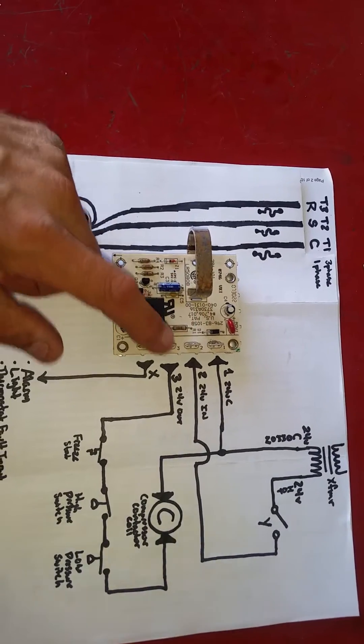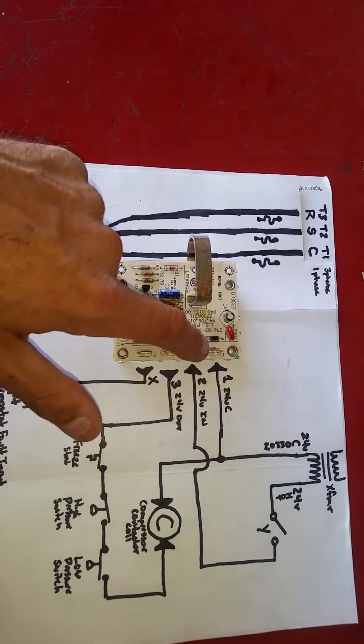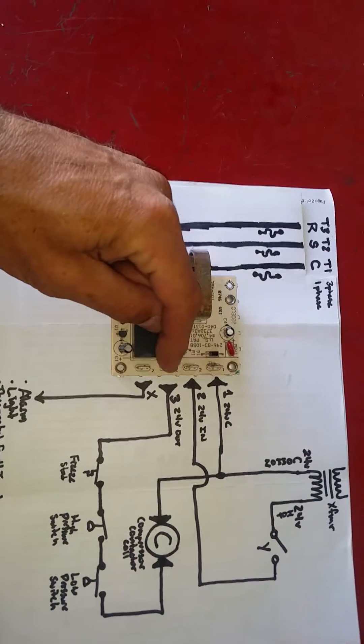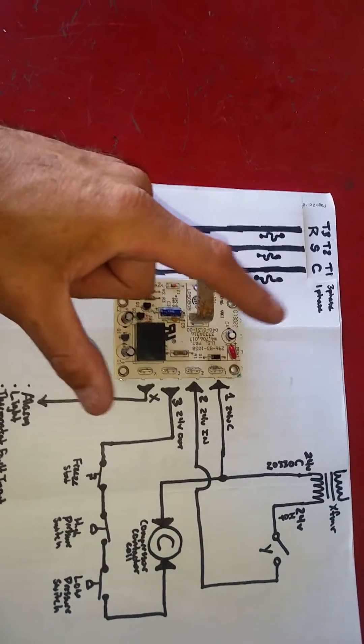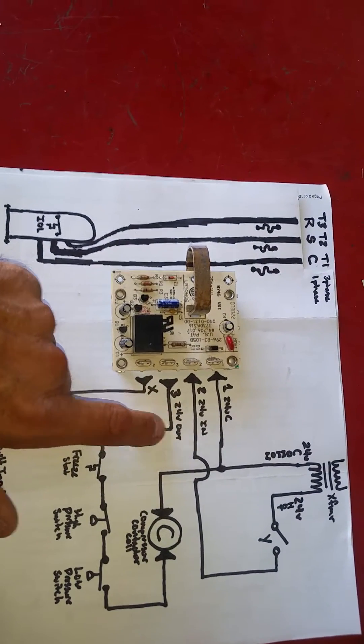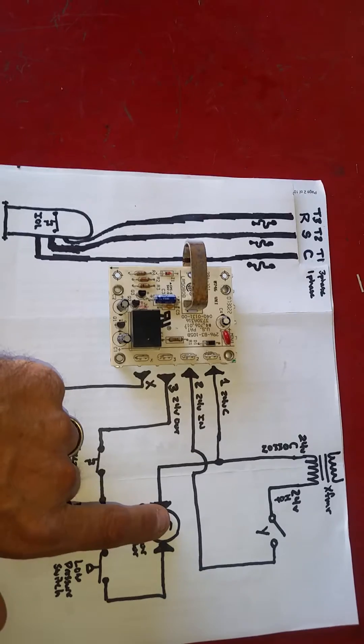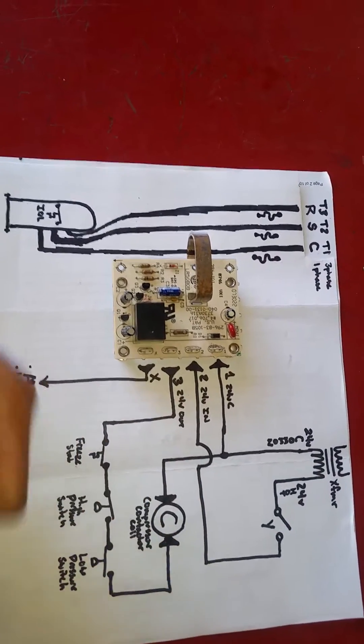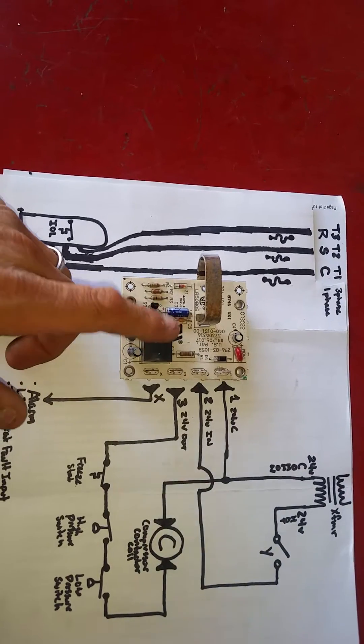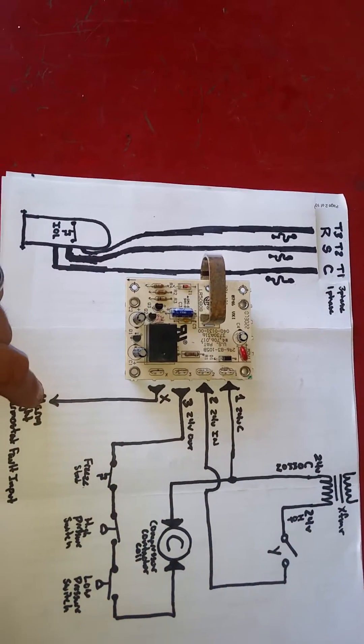When this opens, the 24 volts going to two out the three will no longer be closed. It will now be opened. 24 volts will discontinue out on the 24 volt circuit to the contactor, basically opening the contactor, killing the compressor, and the X terminal more or less becomes a closed circuit. So now 24 volts is sent out to X.